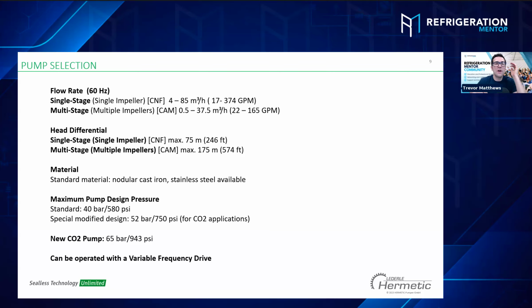So let me make sure I understand this. With a single stage, you can get a higher flow rate, let's say up to 374 gallons per minute or 85 cubic meters an hour, but it cannot move as much head. It can't move as high. Is that right? Yes, it's correct. You get a bigger flow rate, but you can't move as high a total dynamic head, feet of head. Yes, it's head.